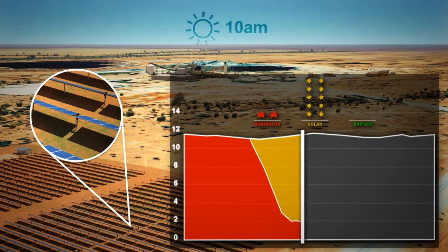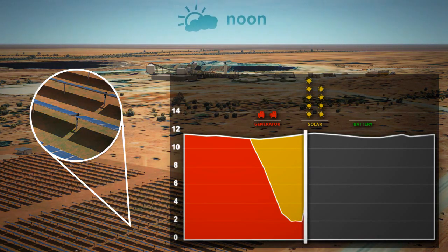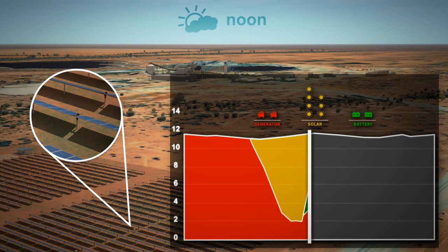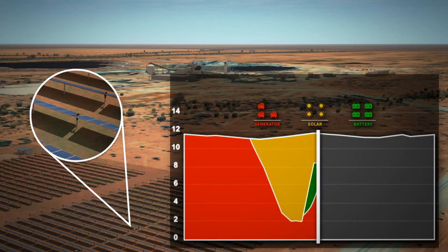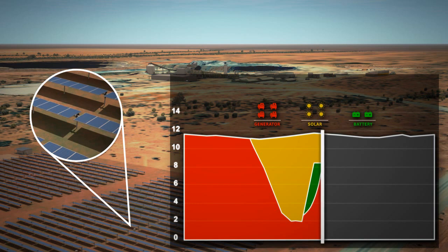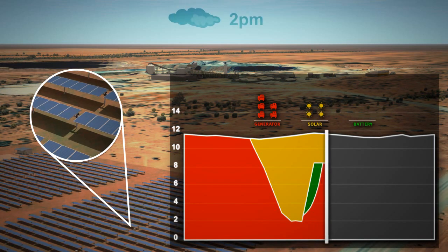When a cloud event occurs, a portion of the energy demand is taken by the reserve diesel capacity already online, with the battery able to meet the balance of demand until new diesel generators can be started and brought online.